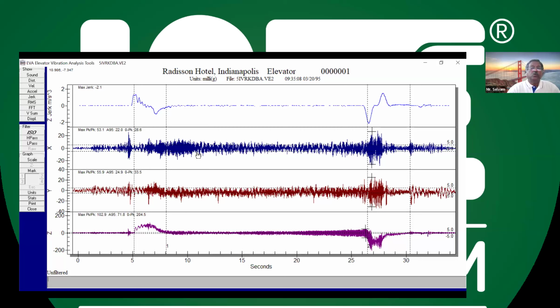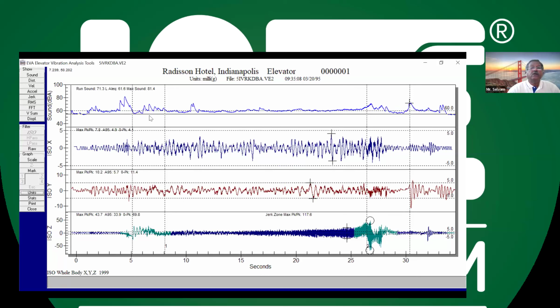For when you want to prove to a customer or consultant, this will give a worst scenario. But this need not be shown. As per the recommendation, the ISO filtered value is when you put a unit setting. If you see the ISO setting, it is 10 hertz. But you can change it. Sometimes some companies, for R&D purposes, can change the cutoff frequency. But ISO mentions 10 hertz only. So when you put ISO 10 hertz, all the unwanted frequency beyond 10 hertz is knocked off.